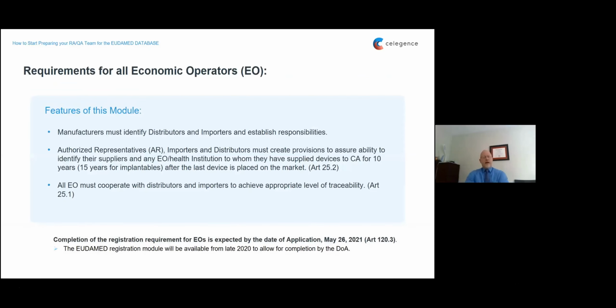So at this time, legal manufacturers are compelled to identify distributors and importers in their supply chains and to establish responsibilities with each of them. They are compelled to identify also authorized representatives and, along with importers and distributors, to create provisions to assure traceability for both upstream and downstream provision. That is, those from which they have received devices and those to which they have supplied devices within their supply chain to the competent authorities for 10 years after the last device is placed on the market, with that obligation actually changing to 15 years in the instance that you're marketing an implantable device.